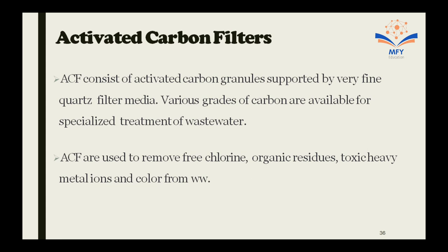Activated carbon filters consist of activated carbon granules supported by very fine quartz filter media, and various grades of carbon are available for specialized treatment of wastewater. Activated carbon filters are used to remove free chlorine, organic residue, toxic heavy metal ions and color from wastewater. The most common absorbents used are activated carbon, peat moss, brown coal, and other cellulose material. This sort of treatment may not only improve taste of water but also protect other water treatment units such as reverse osmosis membranes and ion exchange resins from possible damage due to oxidation or organic fouling.